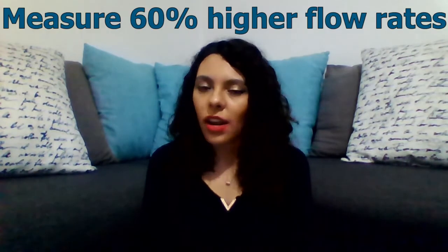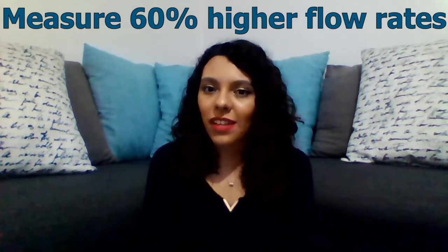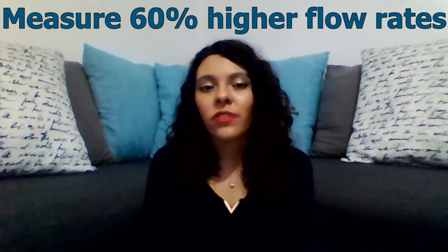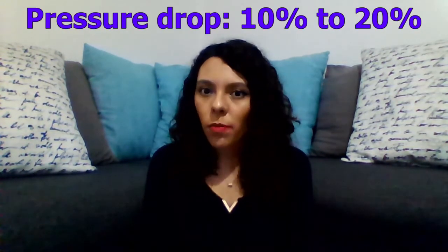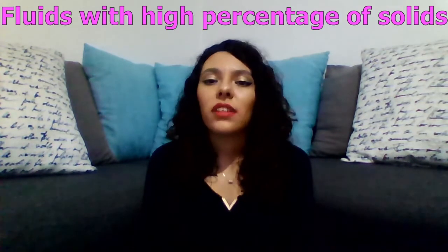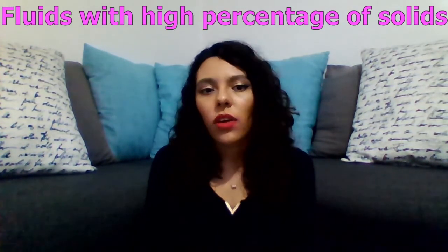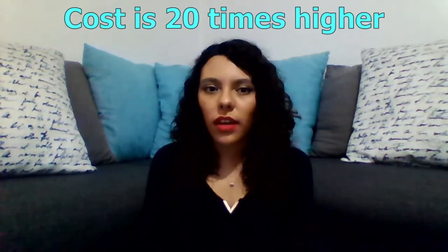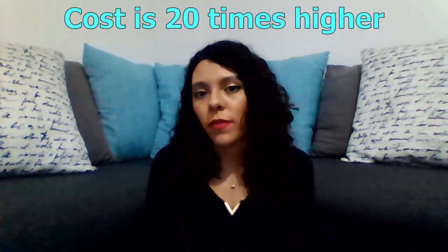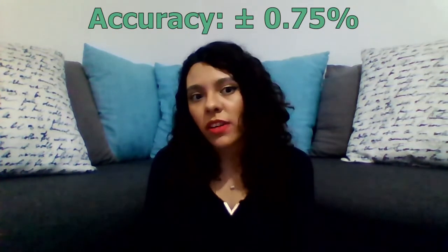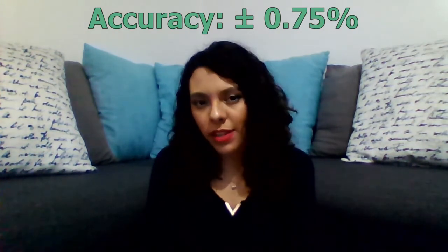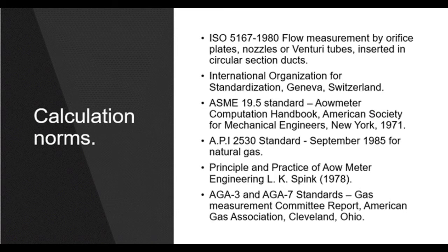The Venturi tube, like the nozzle, needs a previous tap and another one in the center of the smaller section. Among its features is that it allows to measure, like the nozzle, flow rates 60% higher than those of the orifice plate under the same service condition. Having a pressure drop of only 10 to 20% allows the passage of fluids with a high percentage of solids, which, if abrasive, can affect its accuracy. Its cost is 20 times higher than an orifice plate, and it has an accuracy of the order of ±0.75%. For the calculation of all these elements, the following norms are used, which I will explain in future videos.